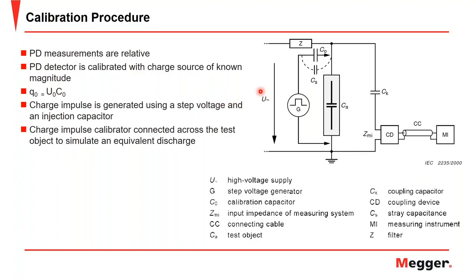And just look at the circuit over here, you can see the circuit is much the same. You have your high voltage source, filter, object under test, coupling capacitor, measurement impedance and coupling device, your cable, and your measurement instrument. The only difference is the calibration procedure, in which you place your calibrator in parallel to the circuit with the object under test, and you have your step voltage generator in series with the calibration capacitor that I spoke of right here.